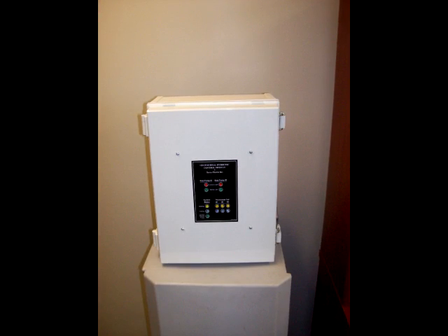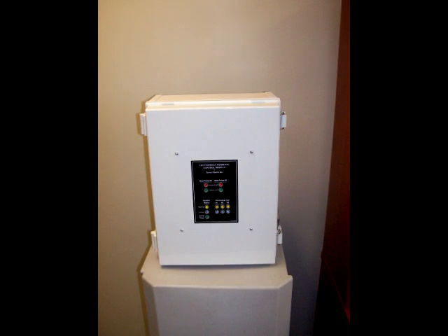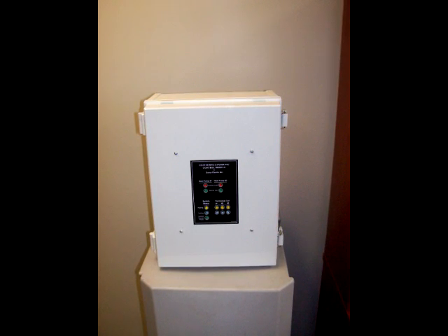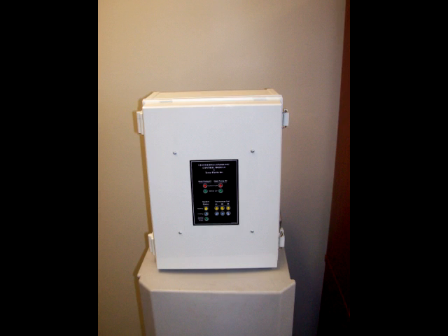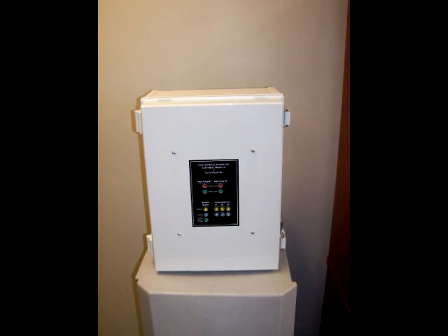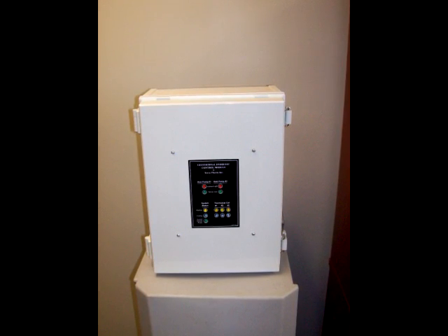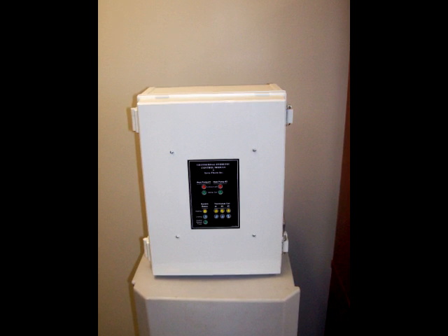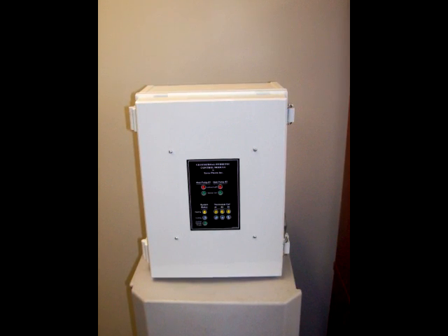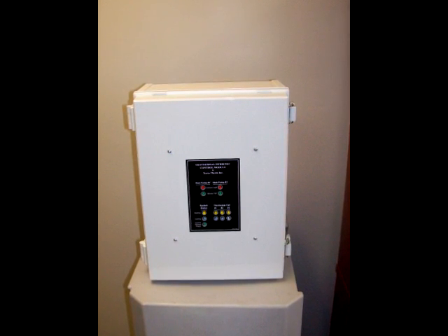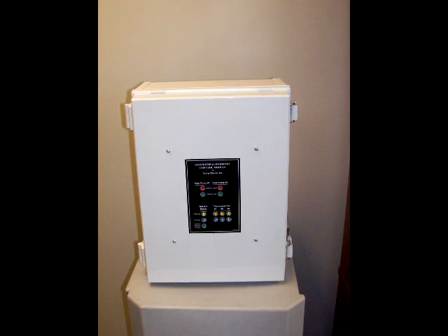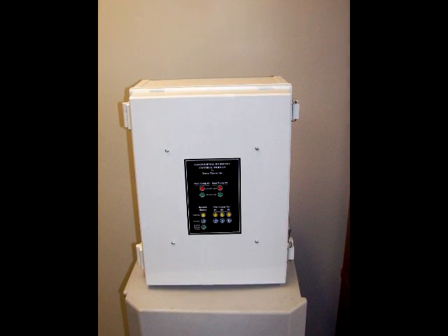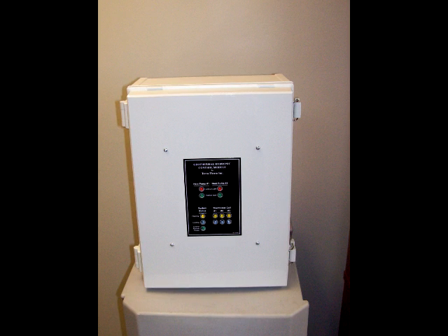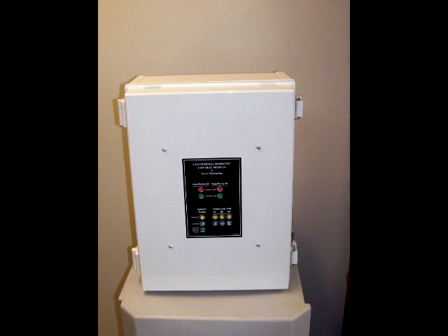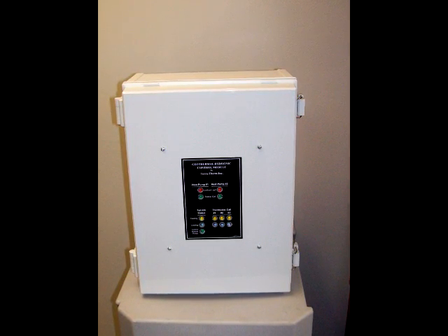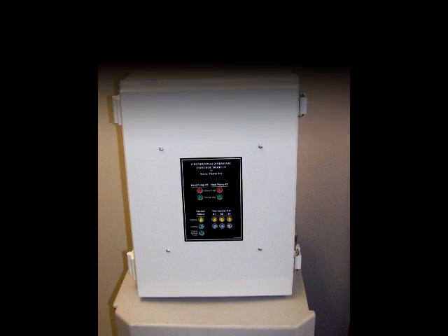Terra-Therm has designed a hydronic control module that offers many features, ensuring a simple and complete control strategy for any geothermal hydronic system that uses a buffer tank. It is designed to control up to 2 heat pumps or 1 heat pump and a backup source, monitor and control the buffer tank temperature in heating or cooling mode, and control up to 3 zones with their corresponding pumps, with the option of controlling additional external zones. Let's go through these features as they relate to the individual components of your hydronic system and explain the benefits of each feature.